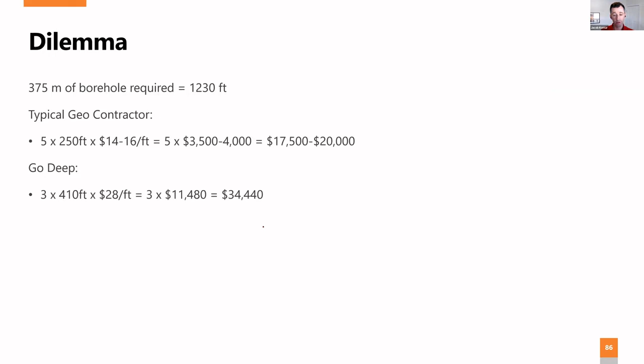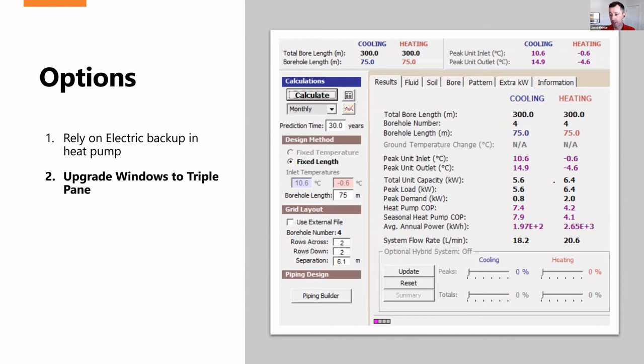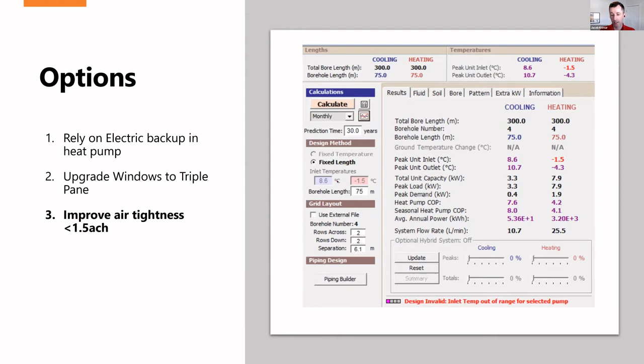There are a few things you can do to avoid that. One, rely on electric backup, much like an air source heat pump, for the 4 or 5 days when ground loop temperatures aren't high enough — the heat pumps can still handle much lower temperatures, they're just less efficient. I can also upgrade to triple pane windows, which reduces the load enough to get away with 4 boreholes, or improve air tightness a bit to achieve the same.